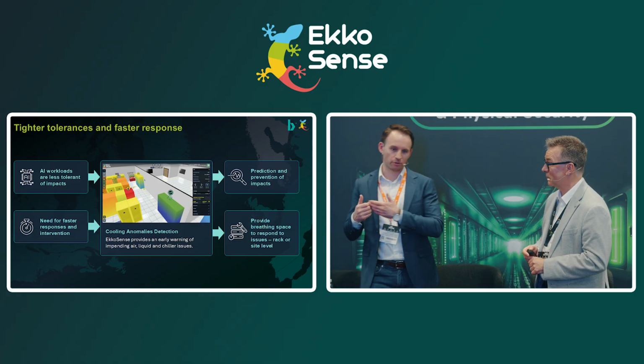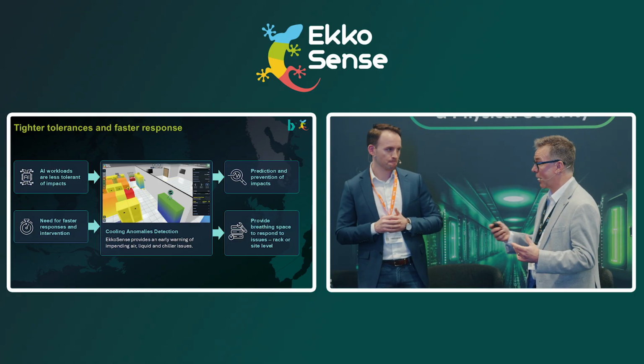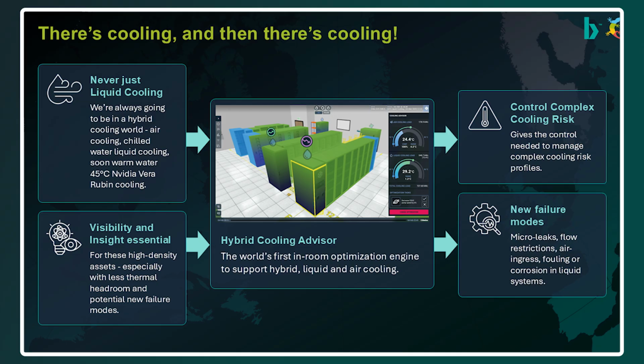So it really translates straight across to the customer side as well, getting ahead of issues. In terms of cooling, we're in this hybrid cooling world and have been for a long time. The NVIDIA guys were talking about the latest Vera Rubin stuff, potentially bringing 45 degree Celsius hot water to the chip. We know direct liquid cooling will only take care of maybe 80% of the cooling load. We still need air in the space to cool CPU compute and networking, so it's a much more complex cooling environment to manage.